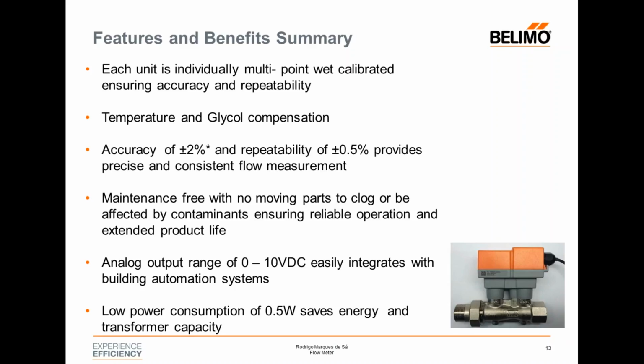The good point is the ultrasonic flow meters are maintenance free, because there are no moving parts. So there's no possibility of clogging or being affected by contaminants or particles, which extends the product life.